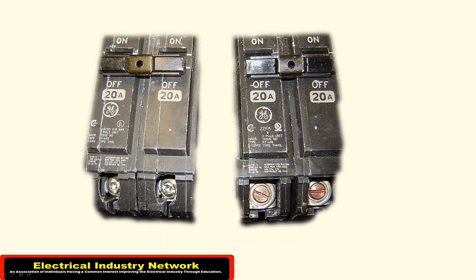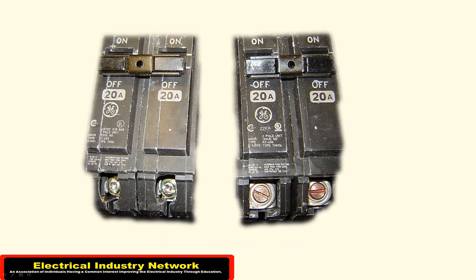In spite of the 22 AIC rating there, let's not even worry about that for now, but way down here it will tell you that it's rated for 240-volt, and back over here it's rated at 120/240.